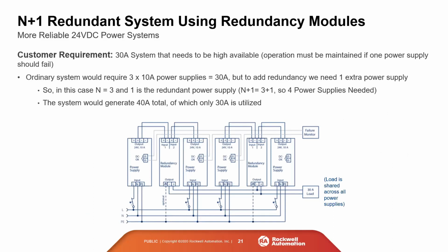So far, we've really only discussed the 1+1. So now let's take a look at the N+1. N, like I said, is just the number of power supplies ordinarily needed to operate the system. So let's take a look at this example. Our customer has a requirement of a 30 amp system that needs to be highly available. Our ordinary system would require 3 10 amp power supplies equaling 30 amps. Therefore, our N would be 3. But we need one extra power supply in case of failure. So that's the +1. So this system would be a 3+1 redundant power supply system.